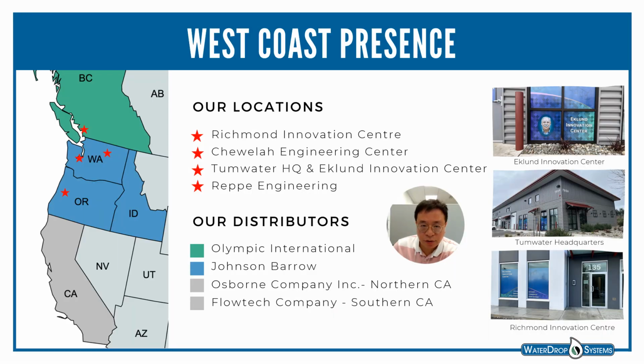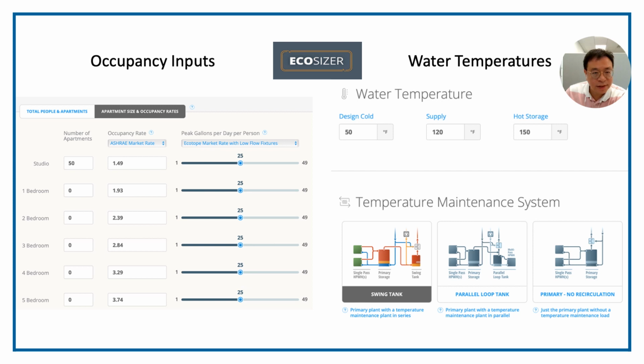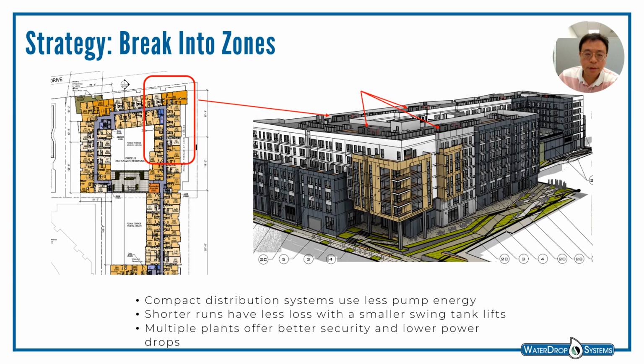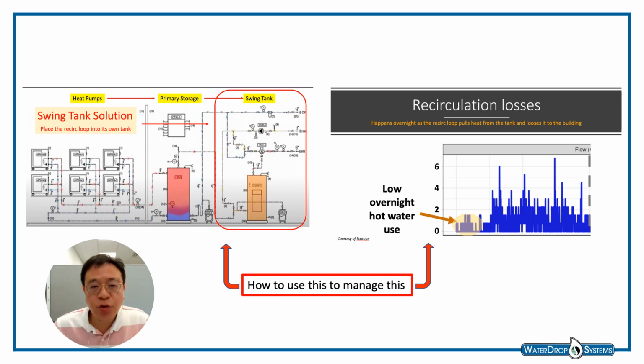Now we start our WaterDrop system along the west coast of North America. When we receive an inquiry from the market, we will size the system by eco-sizer. In large buildings, we tend to break the whole domestic water system into different zones. Zoned distribution systems minimize the heat loss in recirculation and provide flexibility in contingency conditions. With a well-insulated recirculation system, the heat loss is minor compared to the power generation from the heat pumps. To avoid short cycling of the heat pump, we deploy a swing tank to compensate for the heat loss in the circulating pipe.